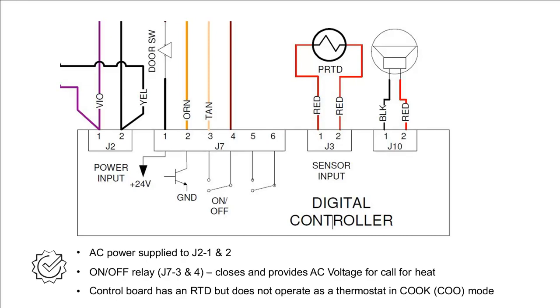Thanks, Andy. So we're going to move on and talk about the actual call for heat, specifically to start with the AC side of the circuit. What you're looking at here is a close-up of our digital controller. You can see the violet wire that feeds operational power to the controller right here. So this has power, operational power, as soon as the unit is plugged in.